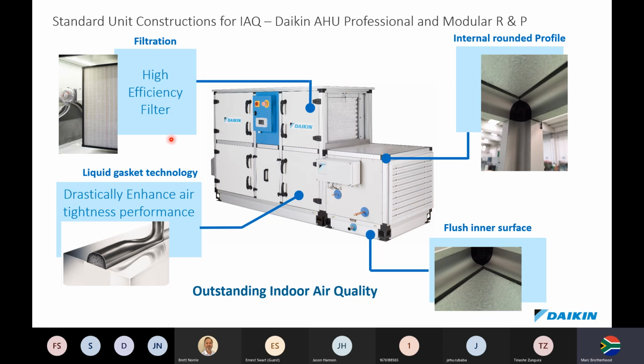High efficiency filters. We have liquid gaskets, so they inject like a liquid silicone in here. When it dries, it creates very good sealing capabilities because of its flexibility. Internal rubber rounded profiles and flush inner surfaces. These are fantastic for hospital applications because they're round. When you get an induced serviceability, there's a very low risk of bacteria living in here, which is going to then feed into the operating theatres or the recovery wards. So these are a huge plus, having these quadrants and the rounded profiles for cleaning purposes. They're very, very hygienic units to use.